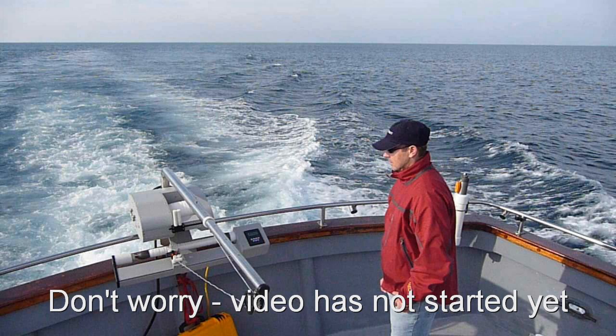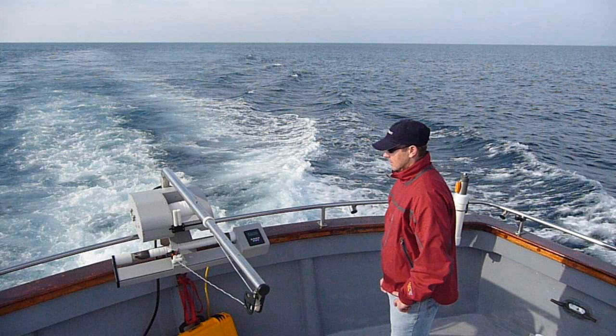Remember, especially for the CTD, that the conductivity cell is glass, so it's quite fragile and should be fine under normal conditions, just with the normal deployment and handling. But if it has a sharp impact against a steel-hulled ship, there is a high likelihood that the conductivity cell can become cracked, and then there'll be problems with the salinity data from then on.